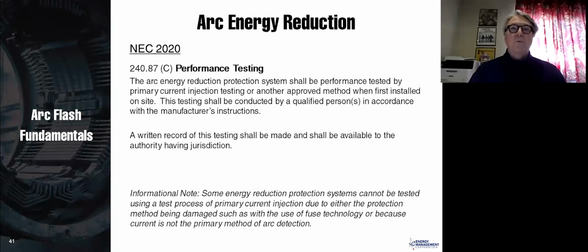Now, this is an interesting one that a lot of people don't recognize and don't do. NEC 2020 240.87(C), performance testing. The arc energy reduction protection system shall be performance tested by primary current injection testing or another approved method when first installed on site. This testing shall be conducted by a qualified person in accordance with the manufacturer's instructions, and you need to have a written method. And at the bottom it says some things cannot be tested. So if you can't test it, so be it. But if you can test it, you're supposed to test it, and it says by primary current injection.